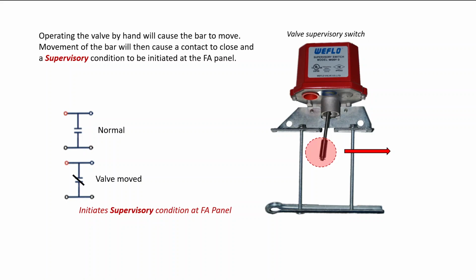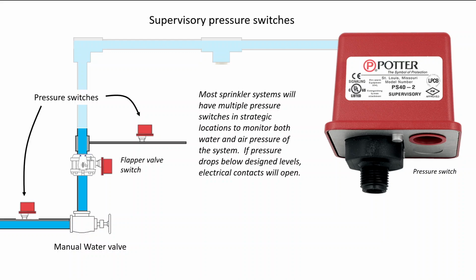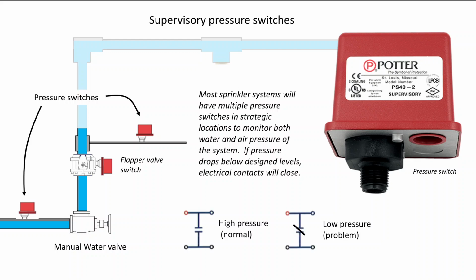This will initiate a supervisory condition, not an alarm. If we look at locations for supervisory pressure switches, they can be varied and numerous. Most sprinkler systems will have multiple pressure switches in strategic locations to monitor both water and air pressure of the system. If pressure drops below design levels, electrical contacts will either open or close depending on the system. High pressure is usually open, and then loss of pressure is usually a connection or closing of a set of contacts. Again, this will initiate a supervisory condition at the fire alarm panel.